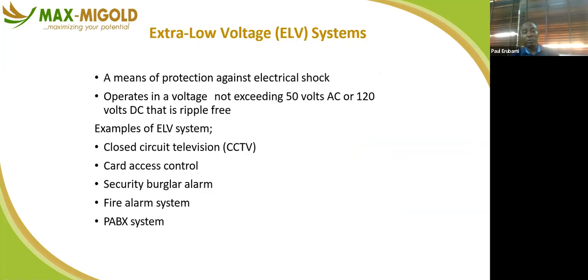In our installation, you cannot underestimate the value of extra low voltage, known as ELV. Most security equipment uses ELV. It's a means of protection against electrical shock. So when you come in contact with them unknowingly, it will not harm you. You may feel a tingling effect on your body, but it cannot harm you because the voltage is very, very low.